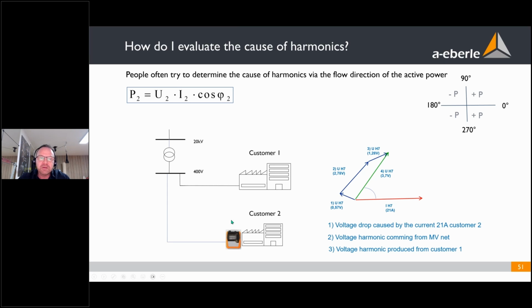Only if your grid has only one consumer and the public grid has no harmonics, then you can use the direction of the power flow. But in this constellation, you do not need an analyzer. It's clear who's responsible. Any time you need an analyzer to find out who's responsible, then it will not help.